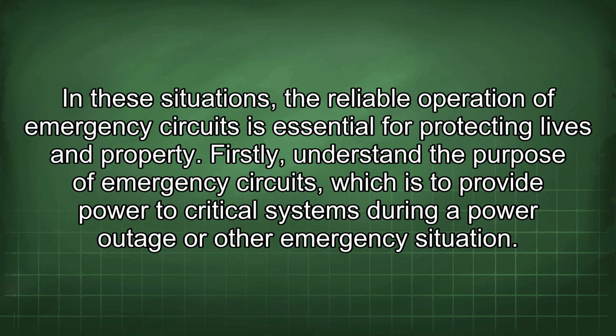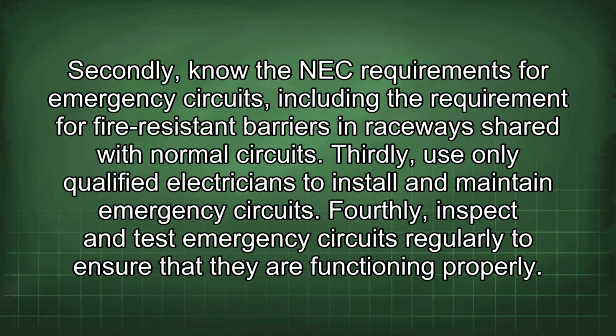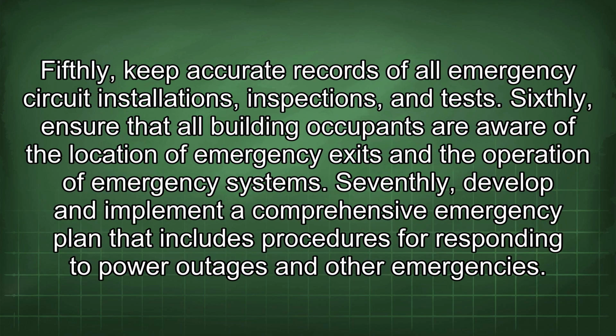Firstly, understand the purpose of emergency circuits, which is to provide power to critical systems during a power outage or other emergency situation. Secondly, know the NEC requirements for emergency circuits, including the requirement for fire-resistant barriers in raceways shared with normal circuits. Thirdly, use only qualified electricians to install and maintain emergency circuits. Fourthly, inspect and test emergency circuits regularly to ensure that they are functioning properly. Fifthly, keep accurate records of all emergency circuit installations, inspections, and tests.